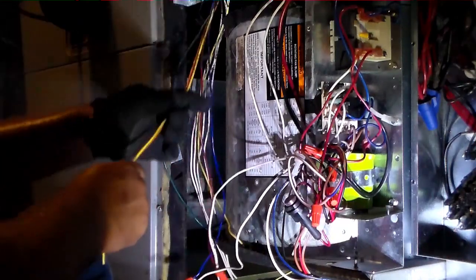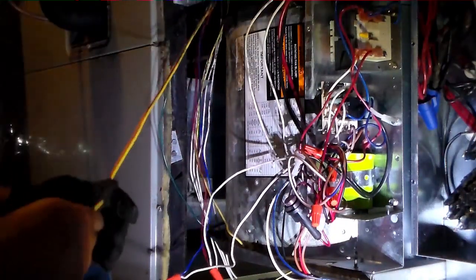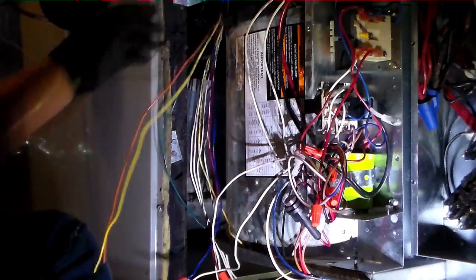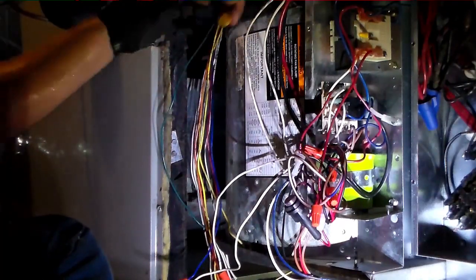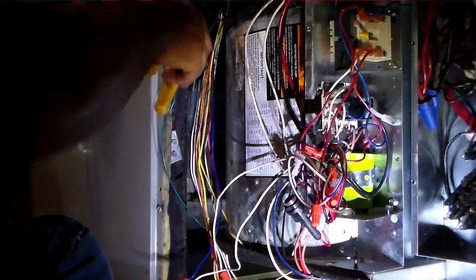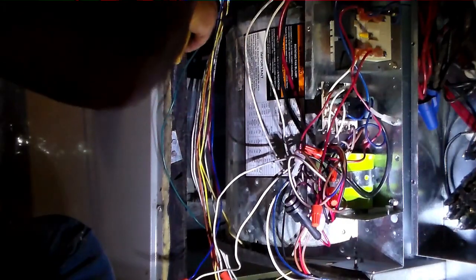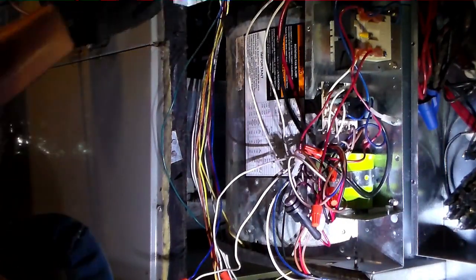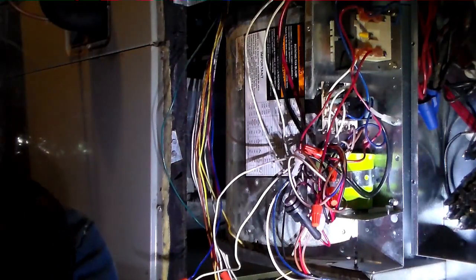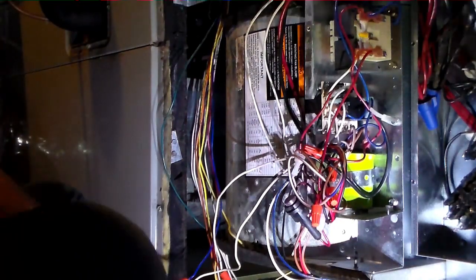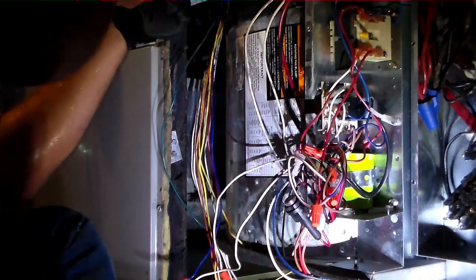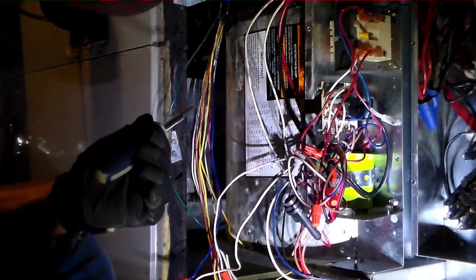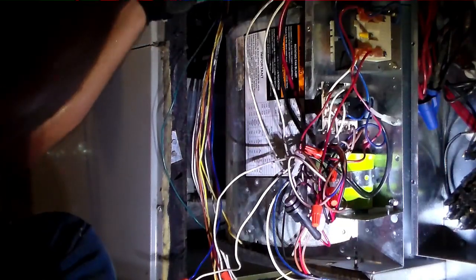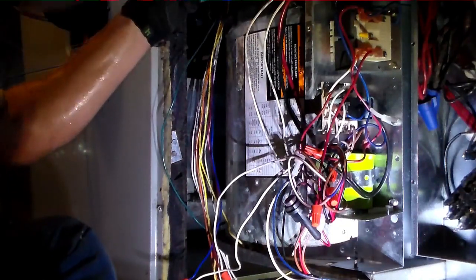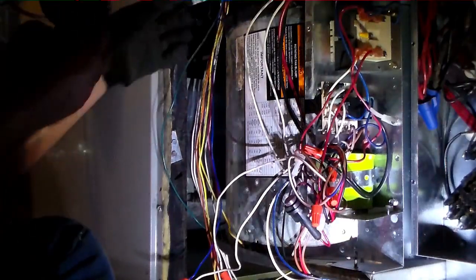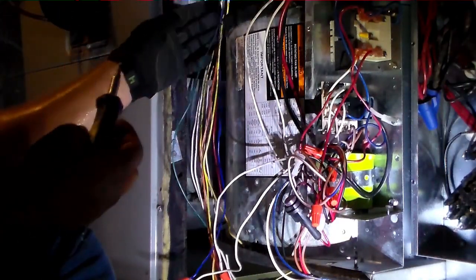So I'm going to cut some of these wires off, take them off the thermostat wire up here because we no longer need them. So we go to yellow, cut the red wire, cut the blue wire. No longer need orange. So we need 4 wires basically: green, white, red, and blue. Green is the fan signal. Red is 24 volt hot. Blue is our common wire. And white is for our heat strips.